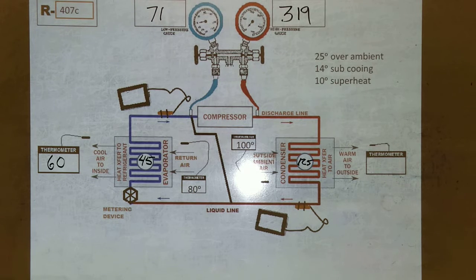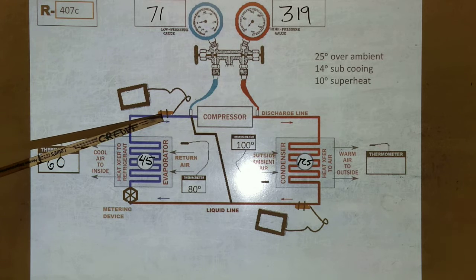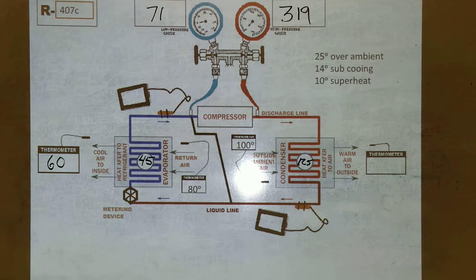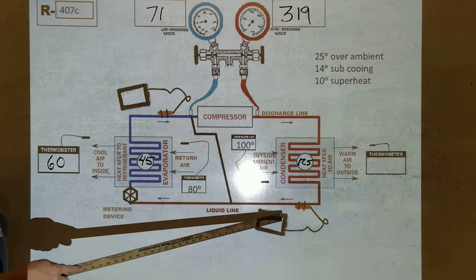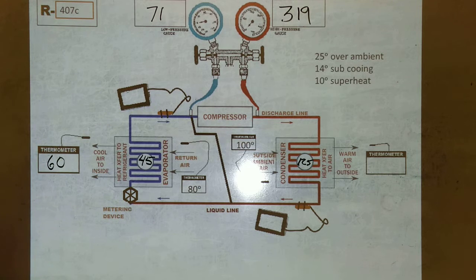Temperature glide. Okay, on your app it says vapor pressure and liquid pressure, right? On the low side, we take the vapor temperature and use the vapor pressure. On the high side, we're checking the liquid side, so that's the liquid pressure. We figure out subcooling with liquid pressure and superheat with vapor pressure.